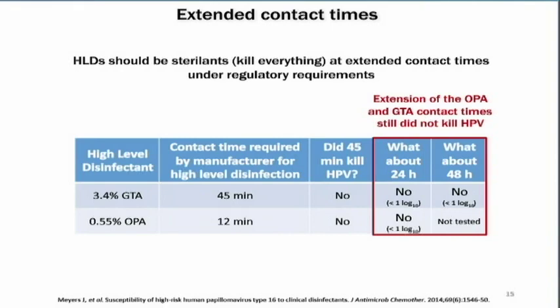So we decided, well, maybe 45 minutes is not long enough. So we tried extended contact times. High-level disinfectants should be sterilants, killing everything at extended contact times under regulatory requirements. So we used the 3.4% GTA and the 0.55% OPA, which, according to the manufacturer, should have a contact time of 45 minutes and 12 minutes, respectively, to be a high-level disinfectant. What we showed was that at 45 minutes, neither was able to kill HPV. So what about 24 hours or 48 hours? We tested the GTA for 24 and 48 hours and the OPA for 24-hour contact times. In all these situations, there was no significant killing of HPV. There wasn't even close to a 1 log reduction of HPV with these long contact times.